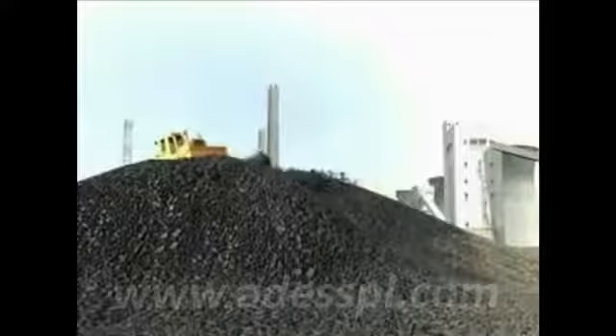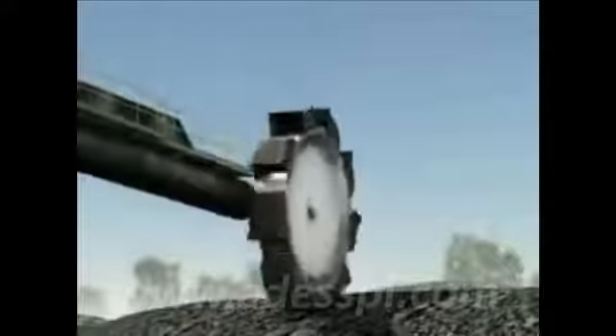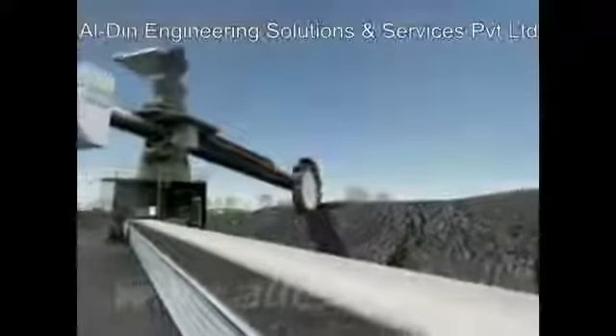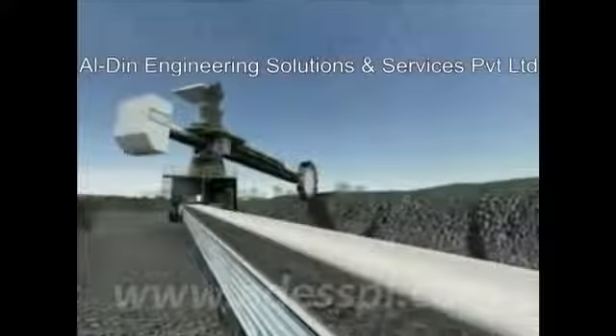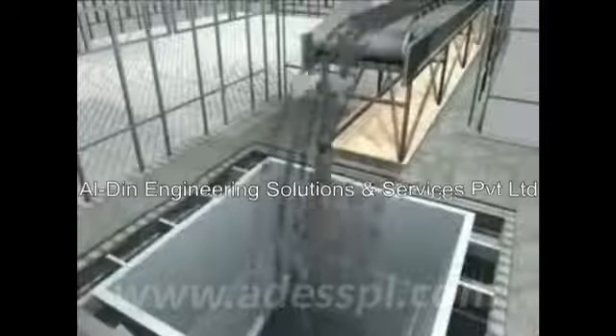Each barge delivers 1,500 tons of coal, enough to keep the plant running for a couple of hours. The plant uses about 21,000 tons of coal each day, so over 1 million tons of coal is stockpiled next to the plant. A device called a stacker reclaimer scoops coal onto a quarter-mile long conveyor that can transport up to 900 tons of coal into the plant each hour. Inside the plant, up to a 30-hour supply of coal can be stored in bunkers.